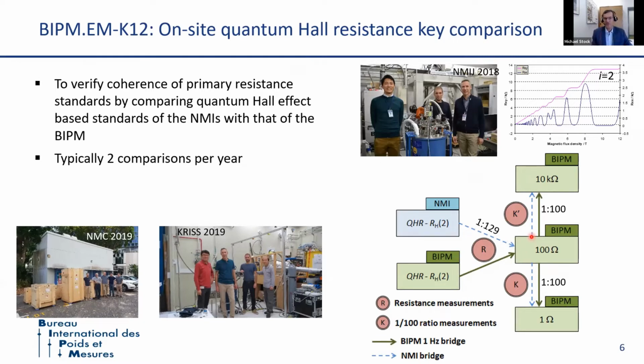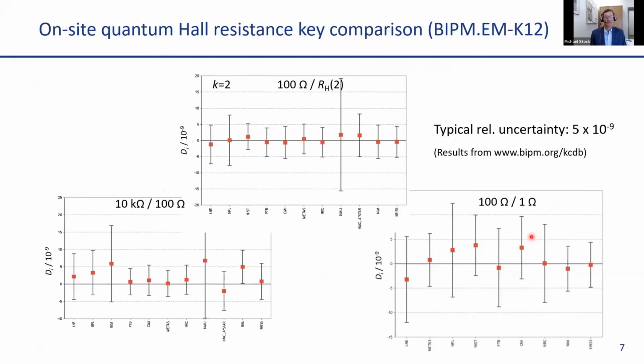The results of these comparisons go into the key comparison database. These are the 3 graphs for the Quantum Hall comparison for the 3 measurements: the 100 ohm resistance calibration, and the 2 1:100 ratios. Here the uncertainties are typically 5 parts in 10 to the 9, with differences which are in general smaller than that.